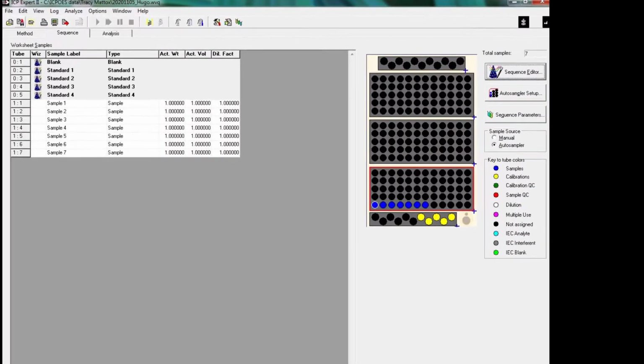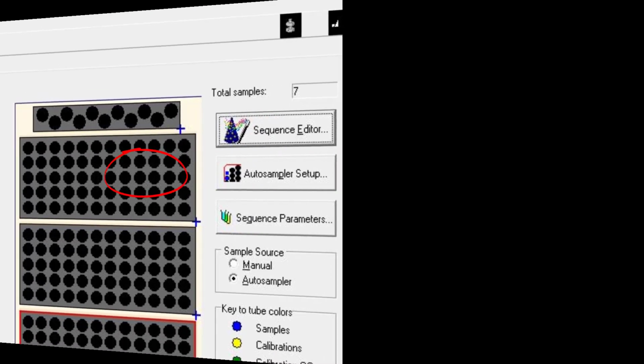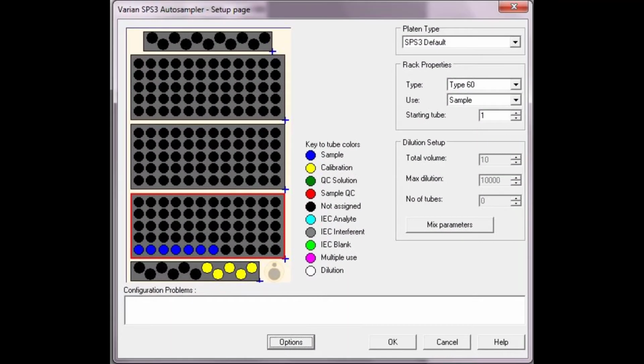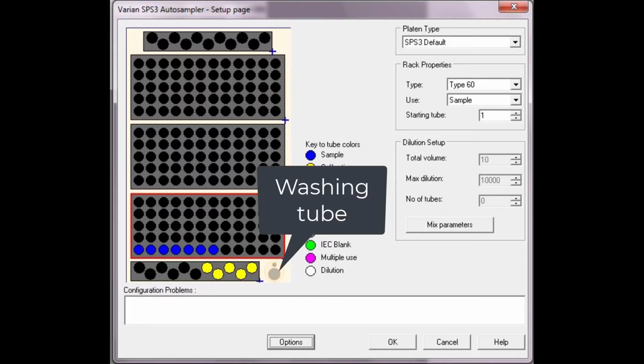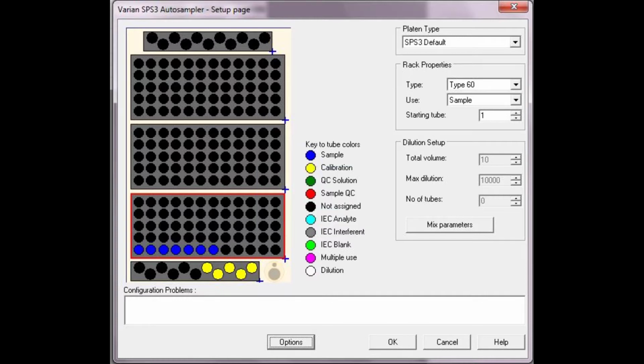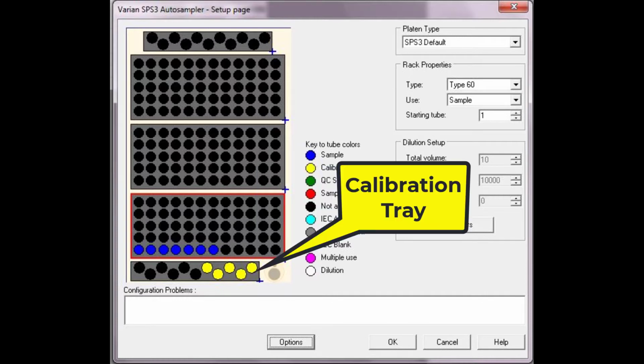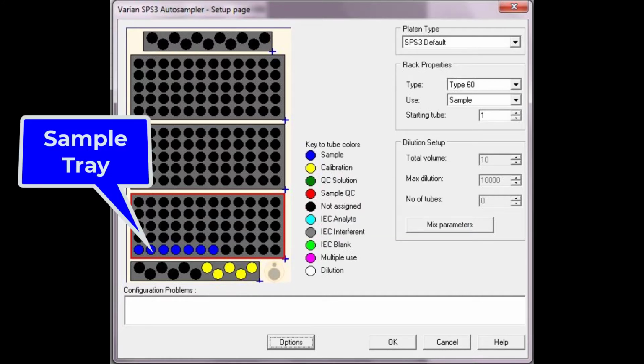Look at the right side of the screen once more and press the button for Auto Sampler Setup. The image on the left is the same from the previous page and shows the layout of the sample trays located in the auto sampler, with the washing tube for the needle grayed out. By default, the calibrations shown in yellow are placed at the end of the sampler, and the samples in blue are on a separate tray.